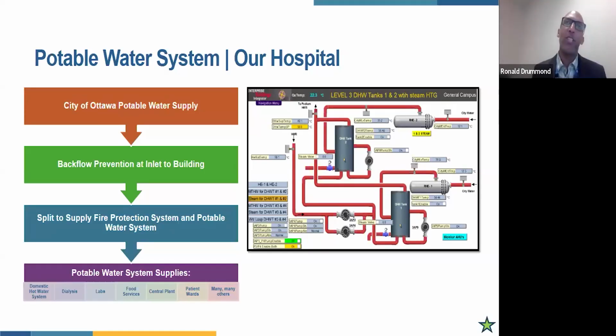And then on that potable side, we deliver to all the various users in the system. So it goes to our domestic hot water system, dialysis. It goes to our labs, our central utility plant, where we do our chilled water, our chemical injection, etc. Goes to the patient wards, amongst many, many others, including food prep. On the right here is a screenshot from our building automation system. This is where our hospital engineers can view and modify the regulation of the hot water in the system. We have a certain set point that we want to achieve. If ever we see that the system is low for some reason, we're able to investigate why or adjust the inlet heating to those devices to make sure that the water circulating throughout the hospital meets standard.